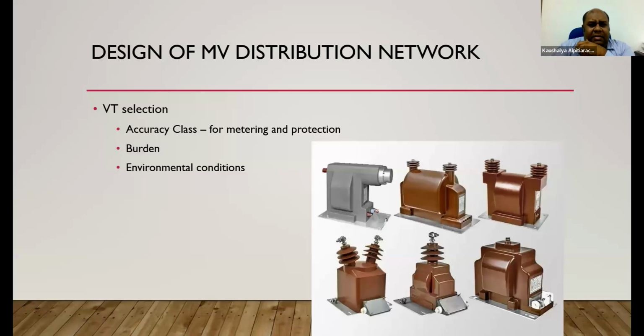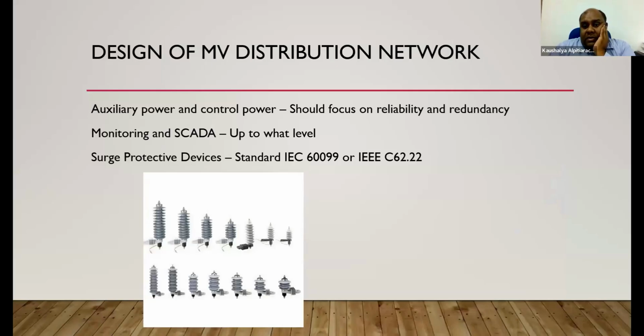VT selection is similar to CT selection: burden, environmental condition, and accuracy class. It's not similar, but goes very closely. Auxiliary power and control power should focus on reliability and redundancy. If you have your control power system for auxiliary supplies and breaker coil or control supply, then you need to provide a continuous supply for the protection system to activate. If your control supply is no longer there when it is needed to eliminate a fault, then there's no point in having such a system. So you should have a redundant supply there, and that should be considered very well during your designs.